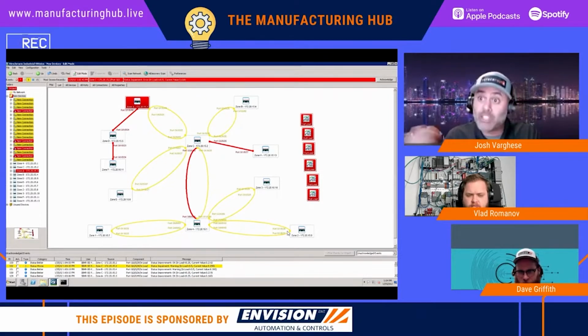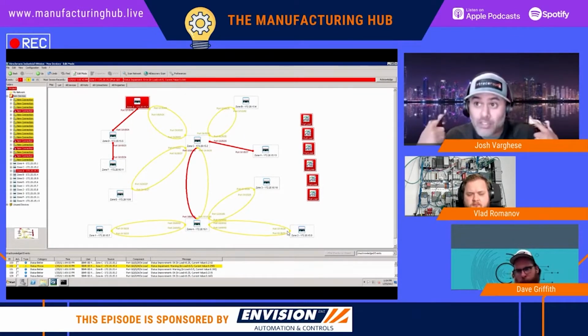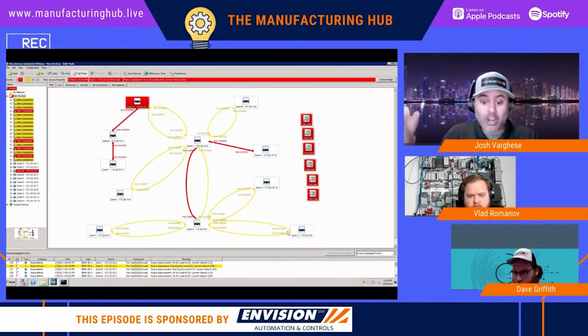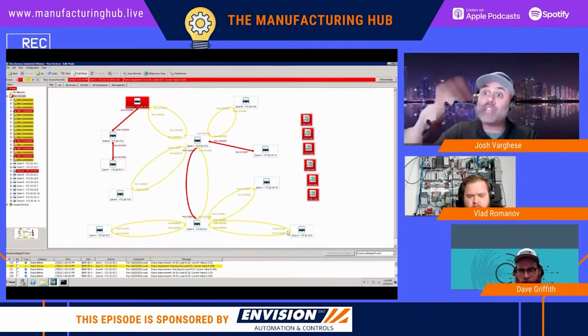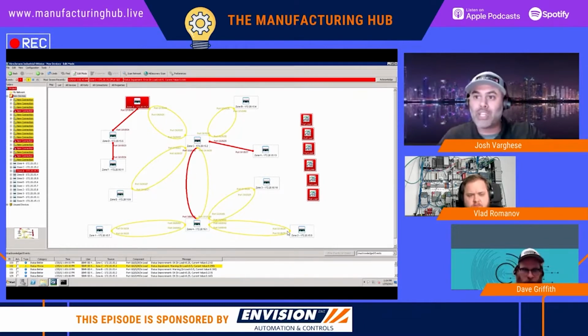PLCs that have been configured to be a consumer of that data, based on their PLC program, they're going to raise their hand. They're going to submit what's called an IGMP join message. And then the second function here, that's what IGMP snooping is. That is the switches running IGMP snooping, listening on this conversation taking place between the queriers and the consumers. They're taking those join messages and building a new database, not the regular unicast MAC forwarding database. It's a multicast forwarding database saying, for this tank level, I got a join message on ports 2, 6, and 8. Next time it comes in, I'm only going to send this traffic to 2, 6, and 8. I'm not going to bother everybody else with it.